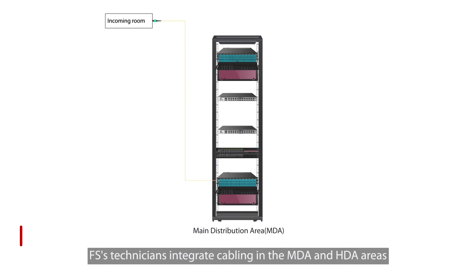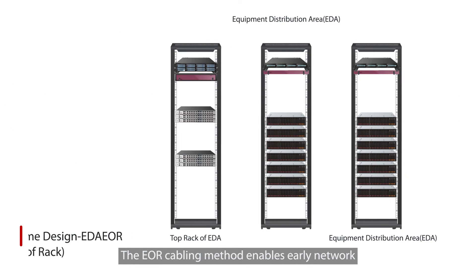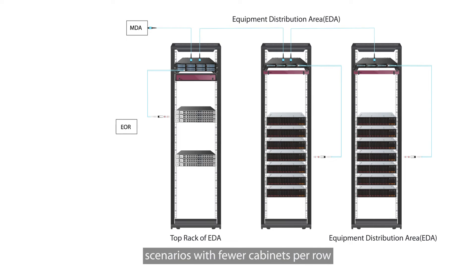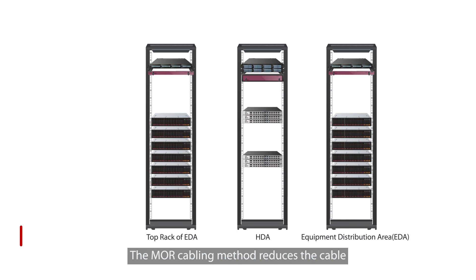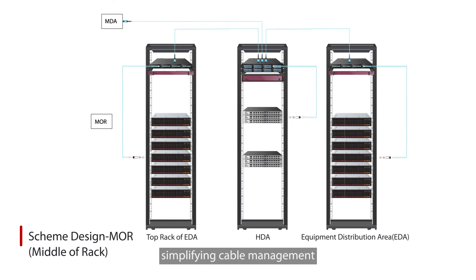FS's technicians integrate cabling in the MDA and HDA areas, combining the cabling methods of EOR or MOR. The EOR cabling method enables early network deployment and is suitable for scenarios with fewer cabinets per row. The MOR cabling method reduces the cable distance from server cabinets to network cabinets, simplifying cable management.